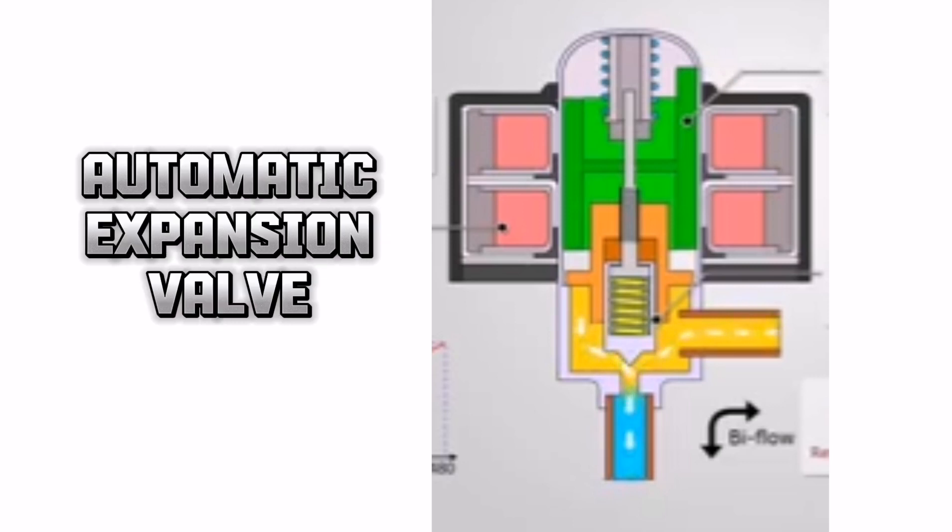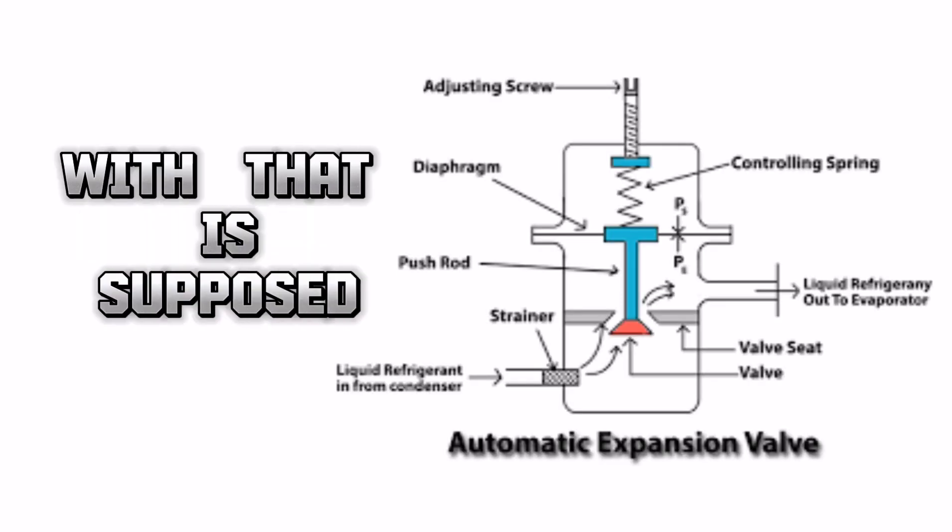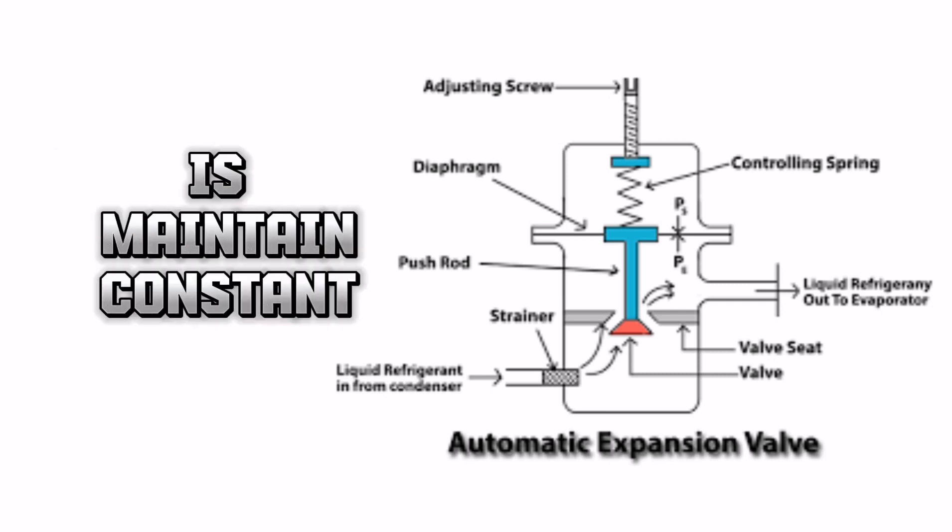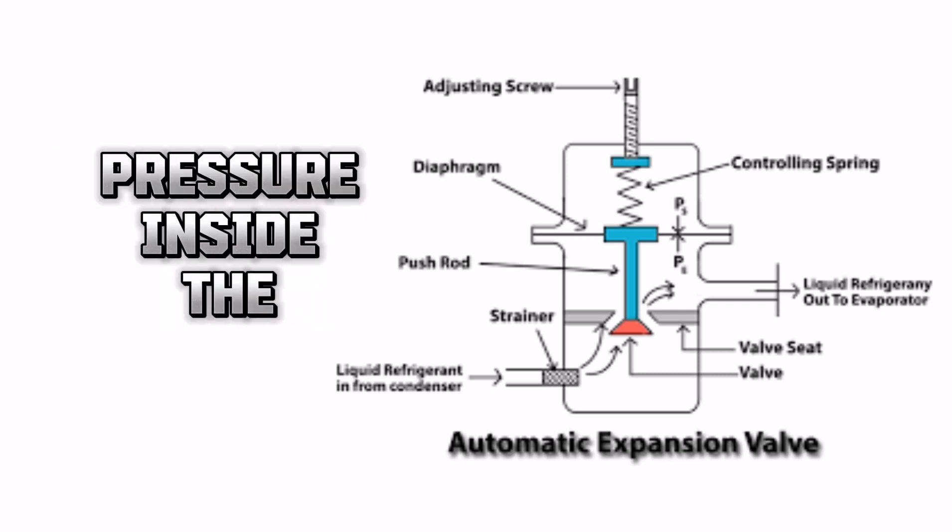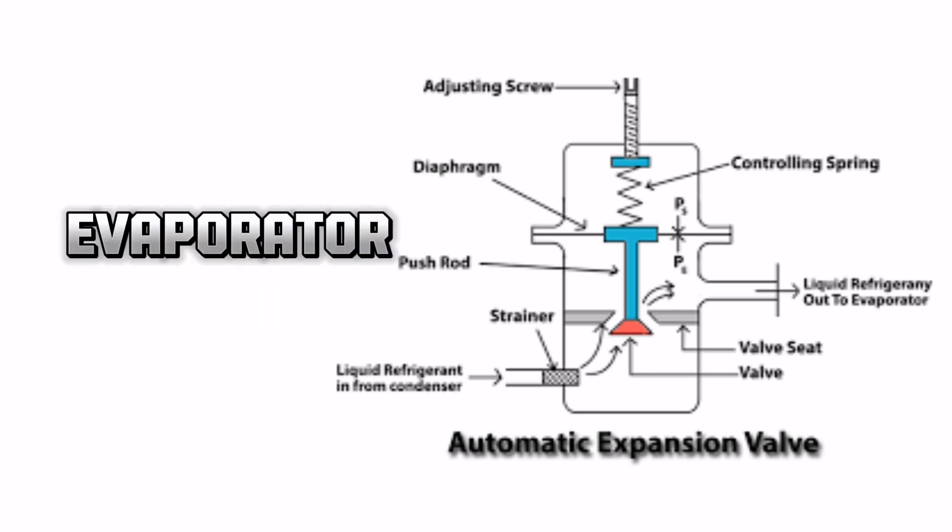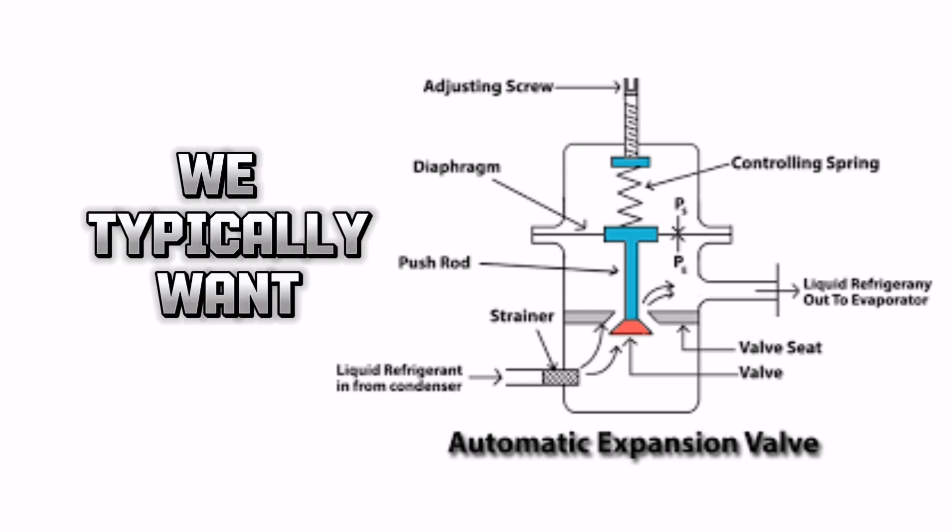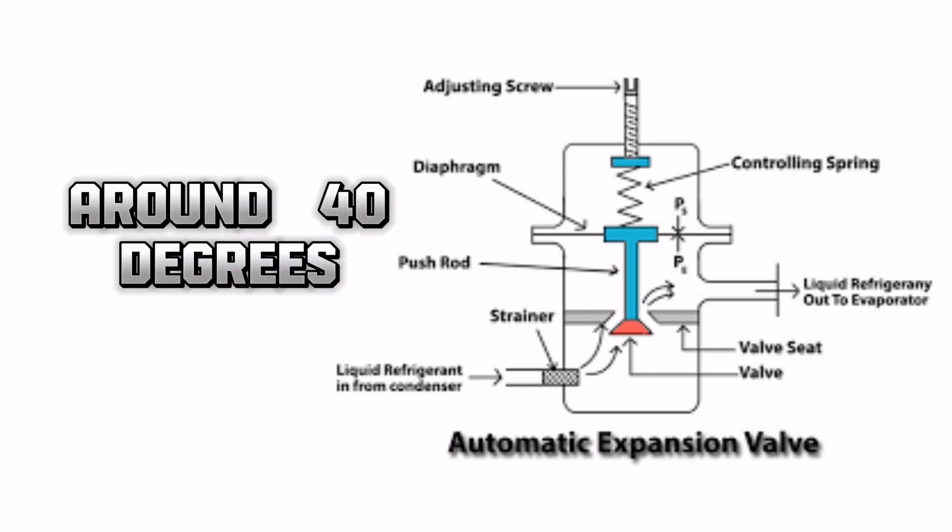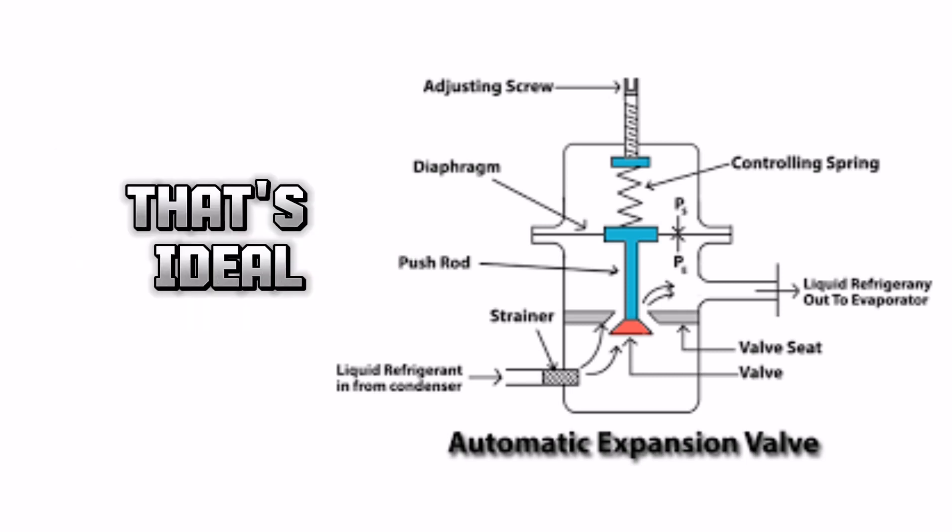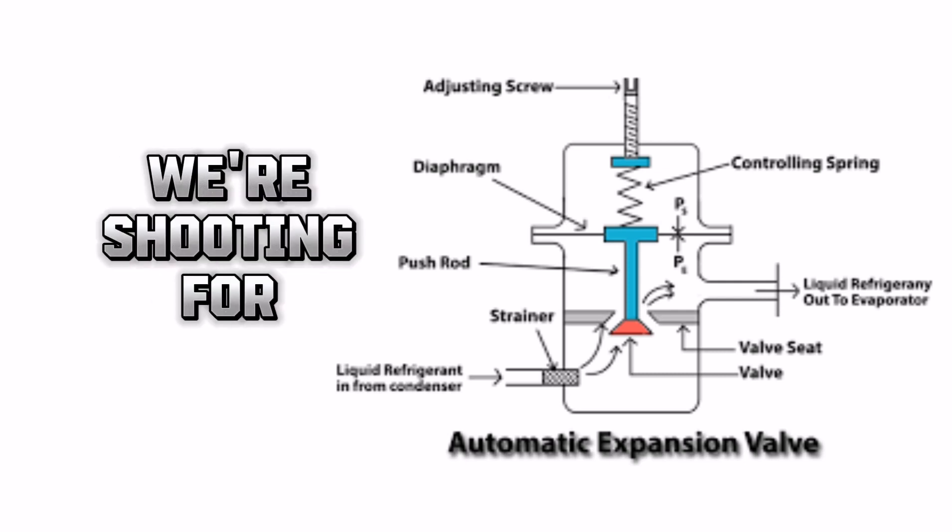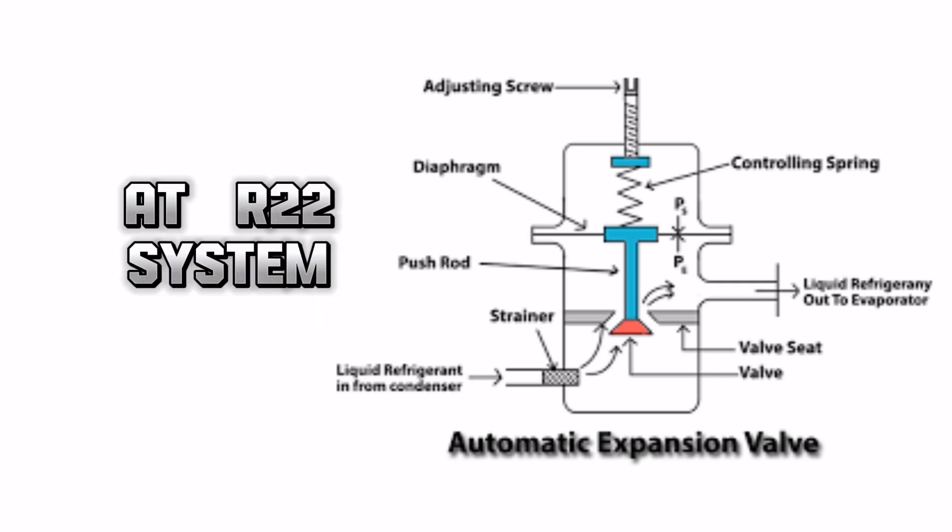Now the other one is the automatic expansion valve. What that is supposed to do is maintain constant pressure inside the evaporator. Pressure. If we think about it, in an air conditioning system, we typically want the evaporator to be right around 40 degrees. That's ideal. That's usually what we're shooting for.